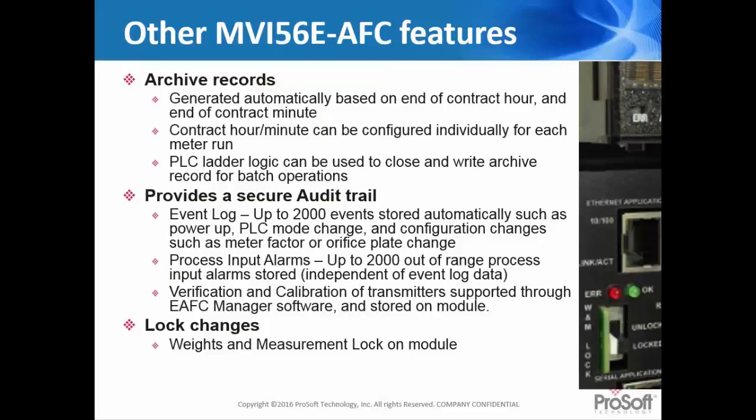There's even a weights and measurements lock on the EAFC module. So if you look to the right-hand side, you see this little switch over here that's marked as a W and M lock. That lock prevents users from changing the calibration or settings of the EAFC module without authorization. So that's again a standard requirement from most flow metering systems.